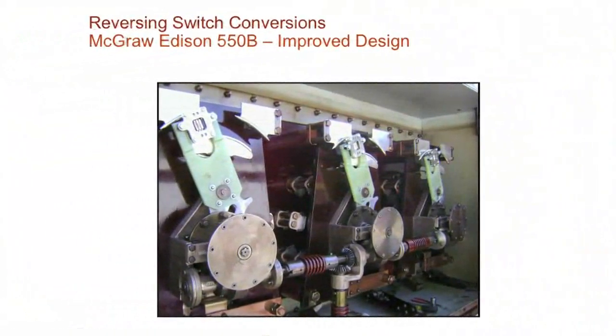This is a McGraw-Edison, what we call 550B. Basically the same type setup. You have the flat blades here. You had the 2 current carrying capacities, and we've changed that to where now you have the rail that it slides on, and then the 6 contact points, the 3 on top, 3 on bottom. Very similar design. We've also changed out the insulating board. We found out that the insulating board was an issue as well inside this particular model.